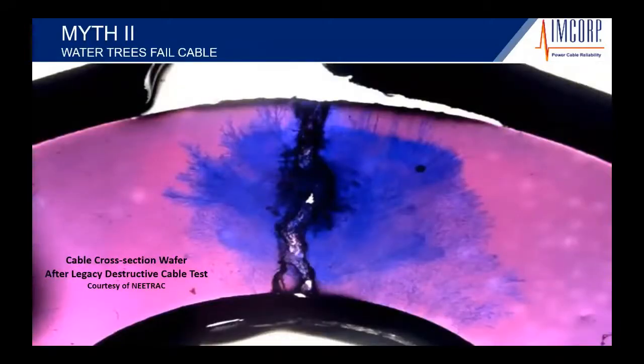Here we have a cross-section of a cable that we took to failure. We used legacy tests. We put overvoltage on the cable system until it finally went to failure. We started doing a cross-sectional dissection of the cable right at the fault, and we dyed the insulation, and we quickly found that there was a water tree associated with it. We consider a water tree a stress enhancement area, and we do know that water trees are prevalent inside of cable systems all the time.